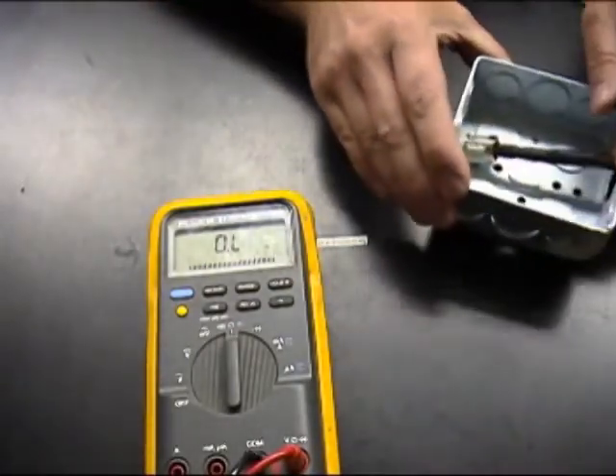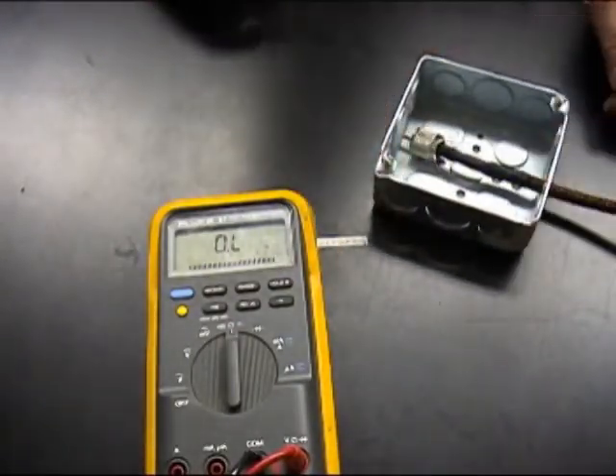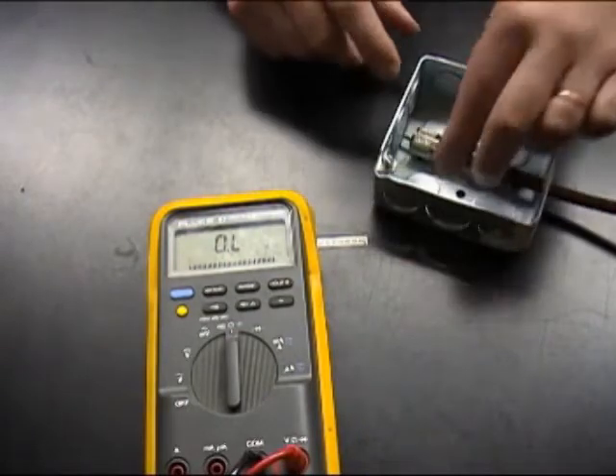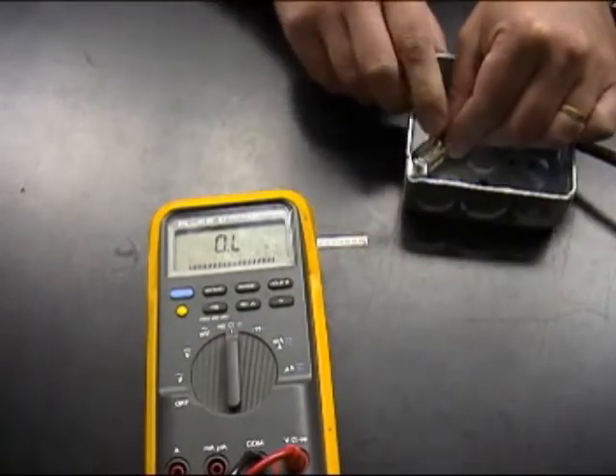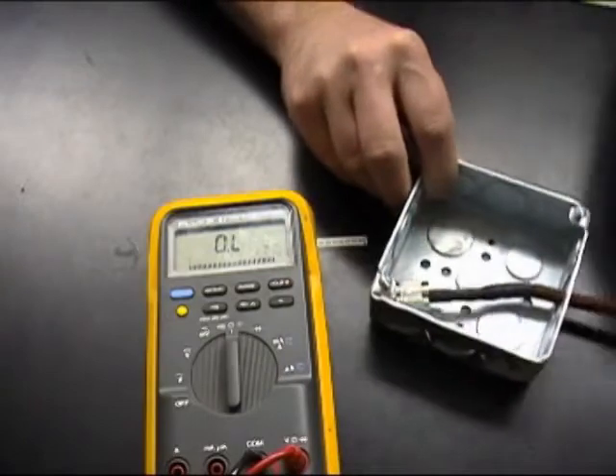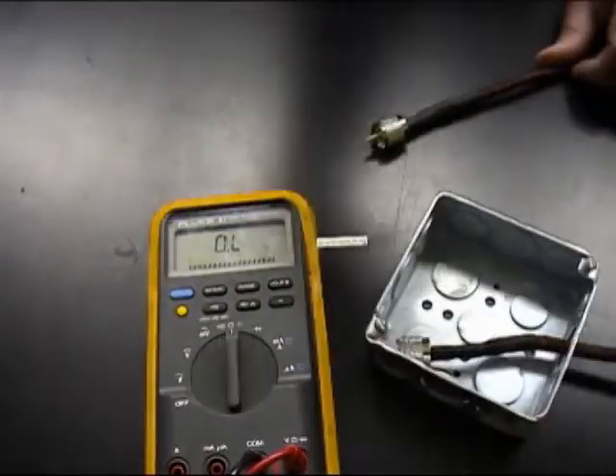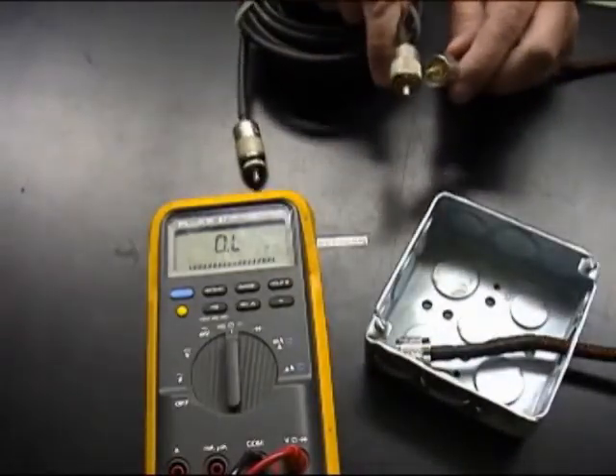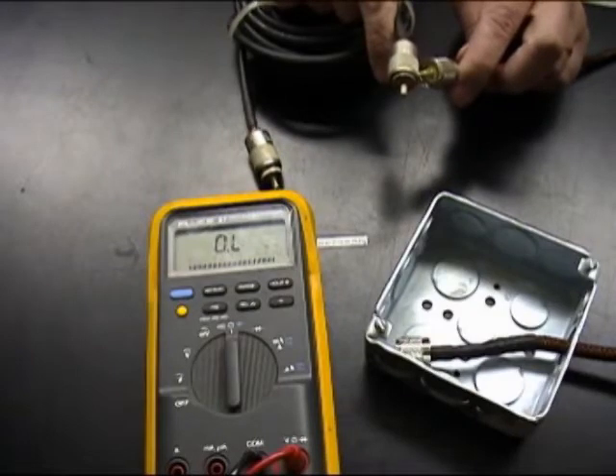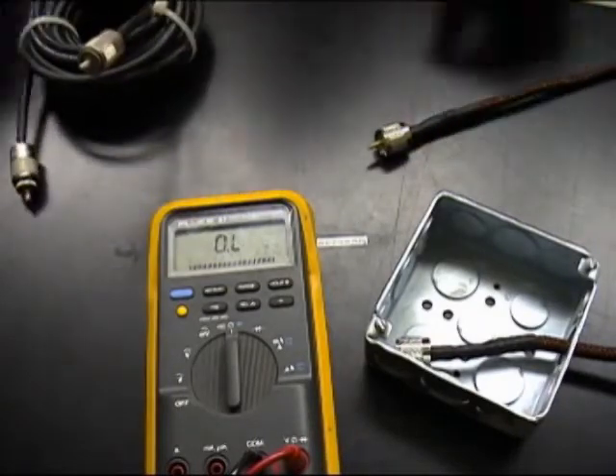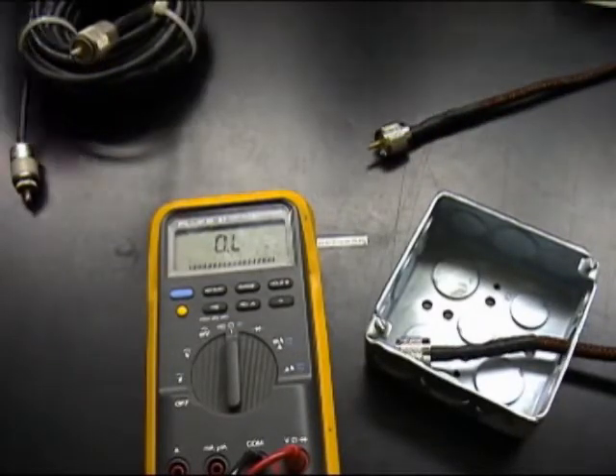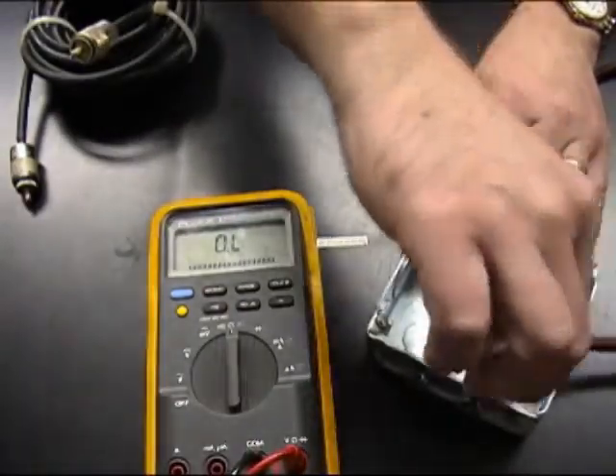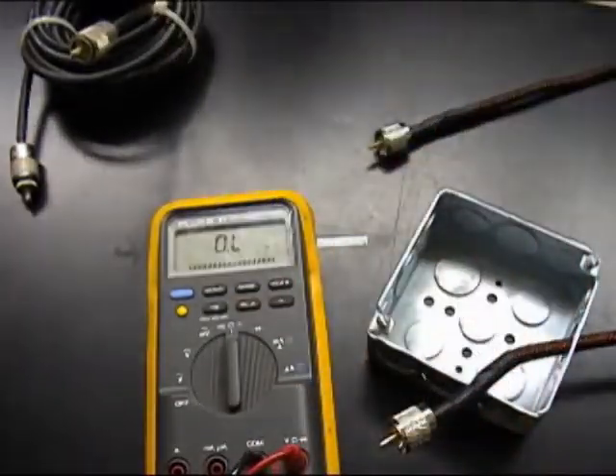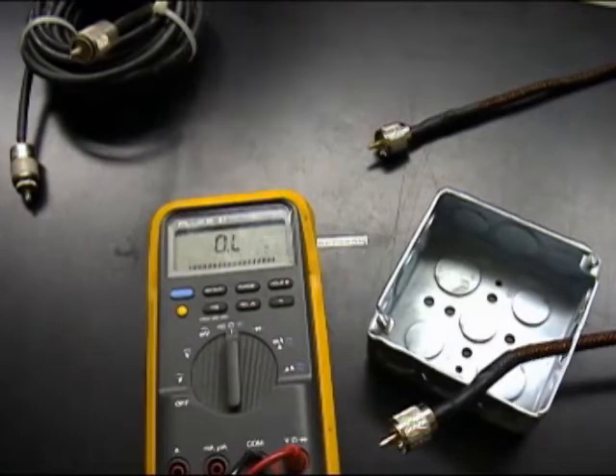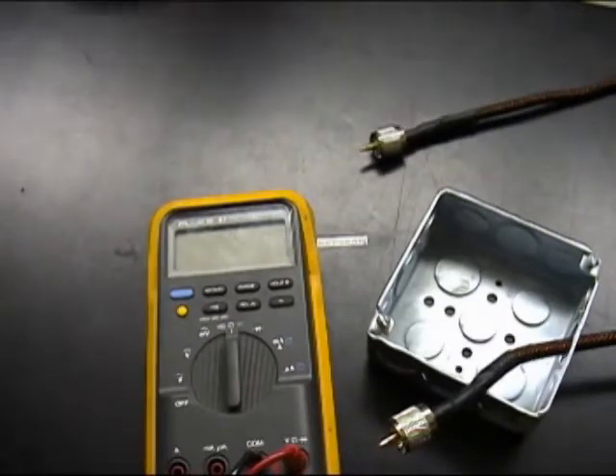First step is to make sure both ends of the cable are open. For example, check if the connector is shorted in a metal junction box or shorted against the connector from another cable. Or, if only one of the connectors is installed, that the braid wire on the other end of the cable is not touching the center conductor. Remember that the insulation test should be run after the installation of each connector.